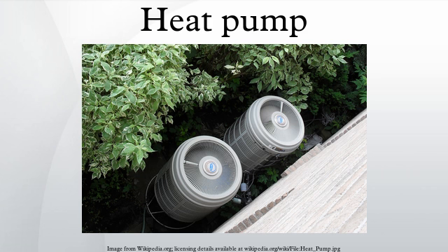When there is a high temperature differential, it takes more work to move the same amount of heat to indoors than on a milder day. Ultimately, due to Carnot efficiency limits, the heat pump's performance will approach 1.0 as the outdoor to indoor temperature difference increases for colder climates. This typically occurs around -18 degrees Celsius outdoor temperature for air source heat pumps.